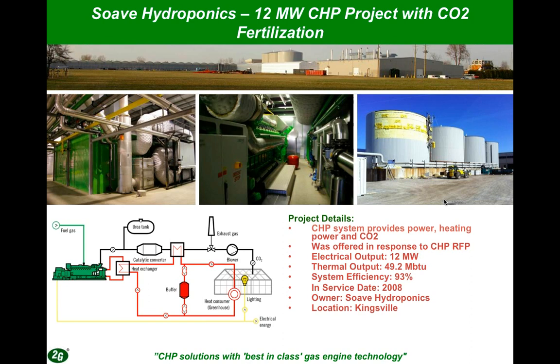At this site, in combination with the 12-megawatt cogeneration plant, the greenhouse installed 4 tanks of 2.3 million liters each, close to 10 million liters of thermal storage. During the day, when the greenhouse may not be able to utilize the heat but the plants do want the CO2, the engines can run. CO2 goes to the greenhouse, power goes into the grid, and hot water is stored in the buffer tanks shown here. At night, when the engines are not running, the hot water is drawn from the tank to provide heating to the greenhouse.